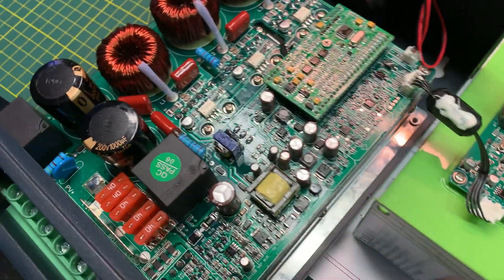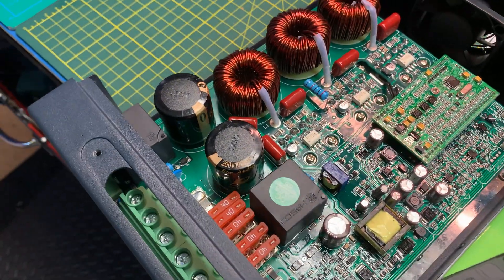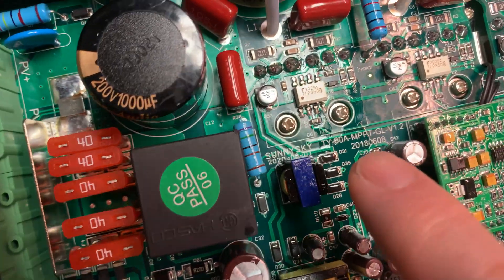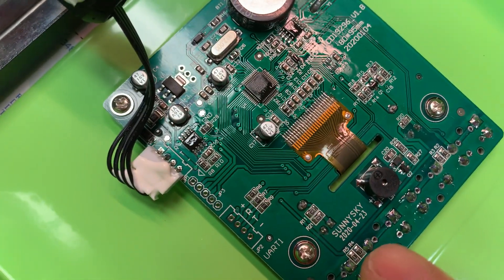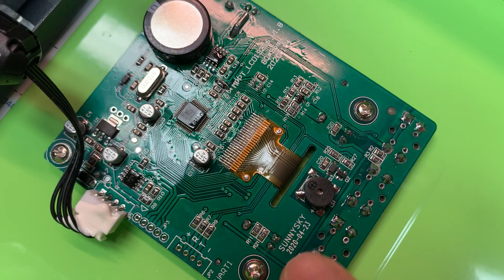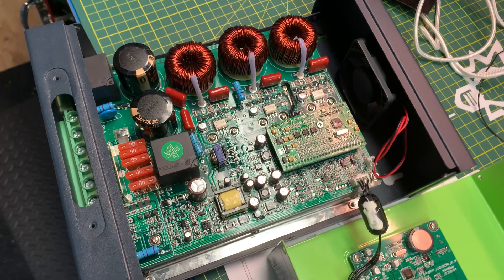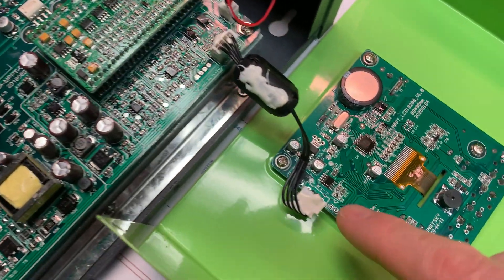I just finished documenting this and I think I know why I can't get anything to talk. This is not what I thought — I thought this would be a rebranded something else, and it may be, but the boards are actually all by Sunny Sky, the maker of this thing, right down to this board where our brain is. I can't quite make out what kind of microcontroller that is, but everything looks like it might actually be their own, and maybe that's why I can't get the Modbus communication to work. I reached out to them — we'll see if they respond back.